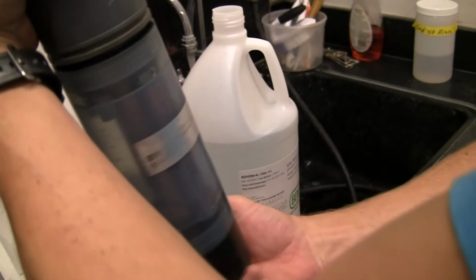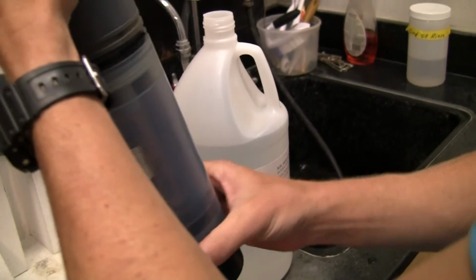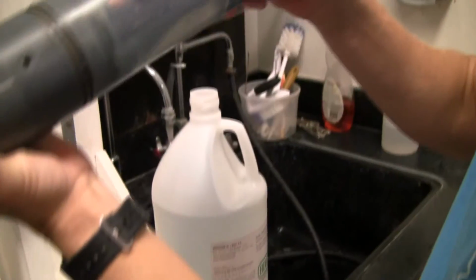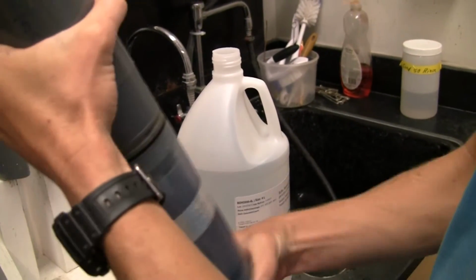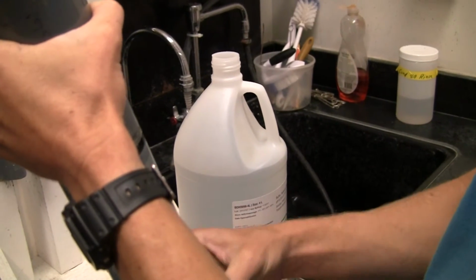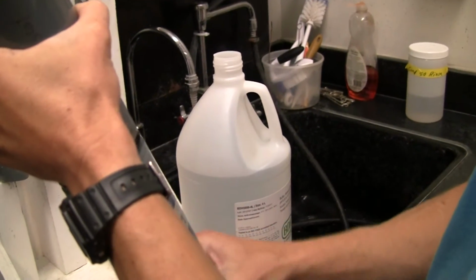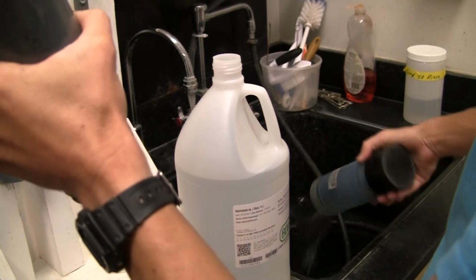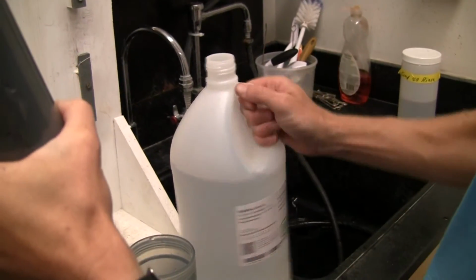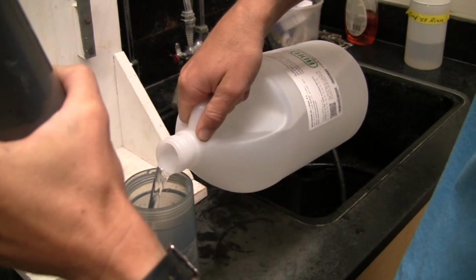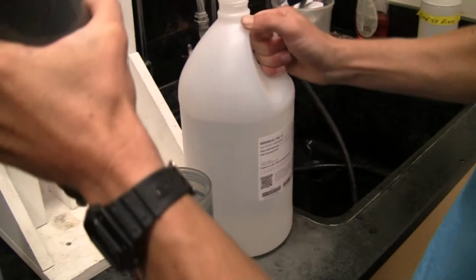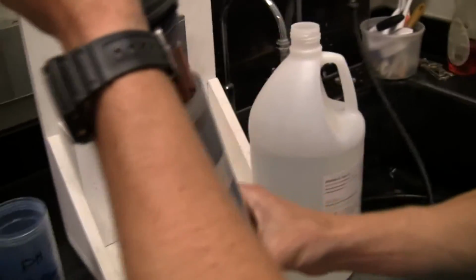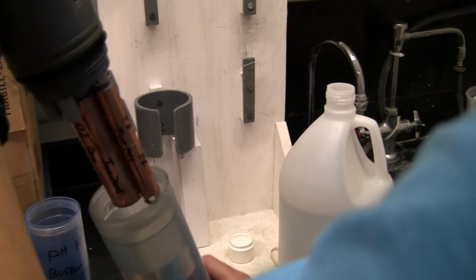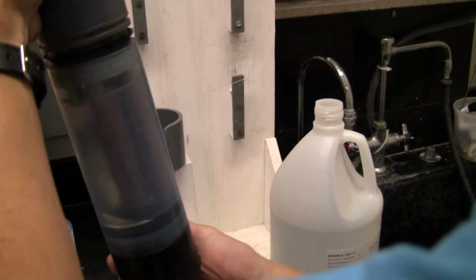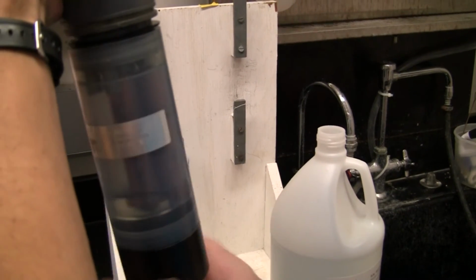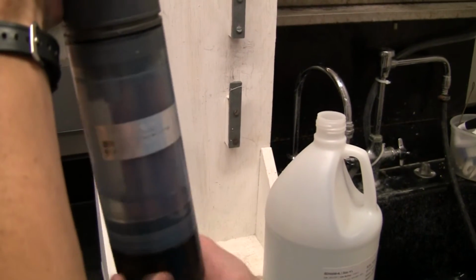So now that we know that it's under the solution, we're going to rinse with the solution. Since we don't have an extra cup for this, we're using the same cup for the rinse and the buffer, with the same procedures applying. Use the rinse. Now that rinse has been used and is thrown away, and more solution is poured in, and this is now going to be the true buffer. Again, verify we have enough solution for the sensor to sit in the solution, which we do.